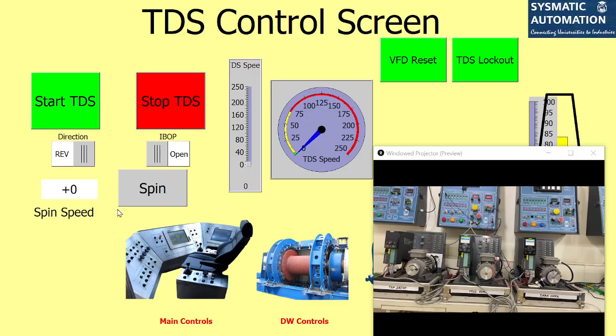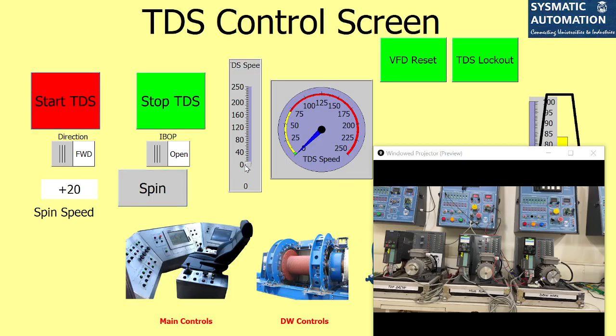If I stop, then there's the option of spin. In spin, I can put any values. For example, usually you put 20 RPM as a spin. Then I have to click on spin and hold it. The motor will spin either in reverse direction, or if I slide it to forward, it will rotate in forward direction, right? Then once I start, I give the reference, for example, 80 RPM. This is 80, so the top drive motor should be running at 80 RPM.